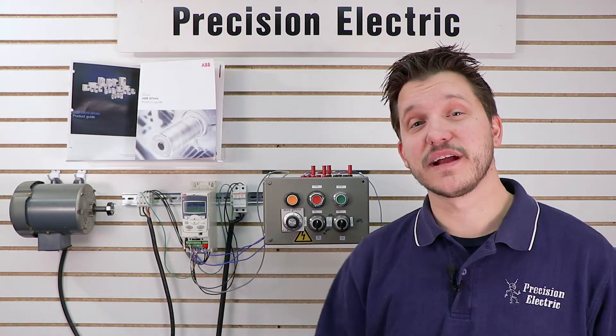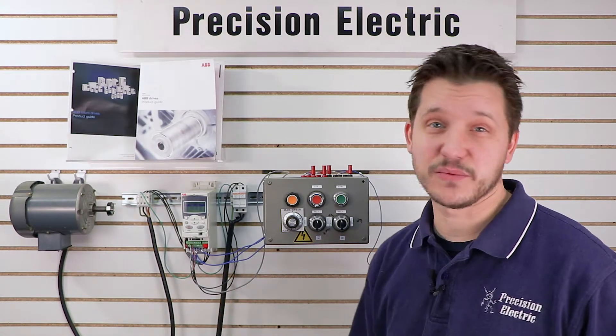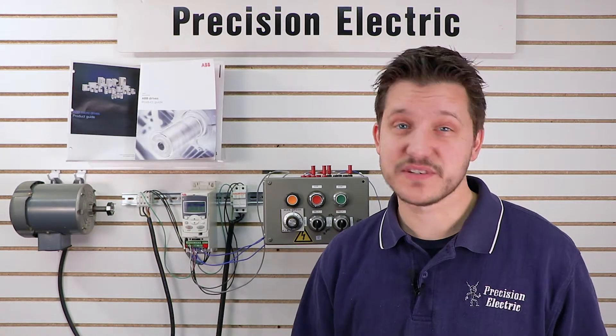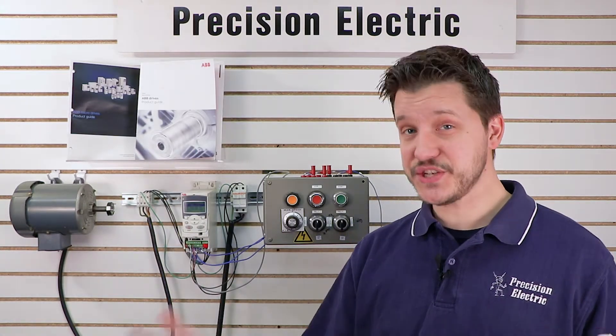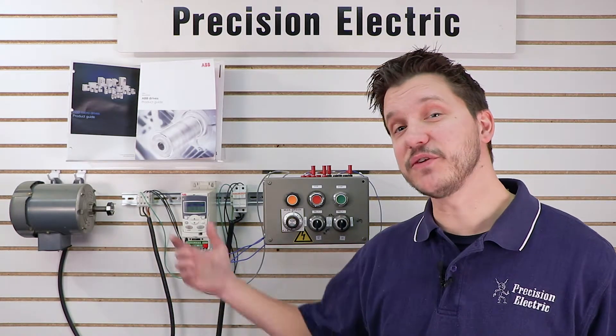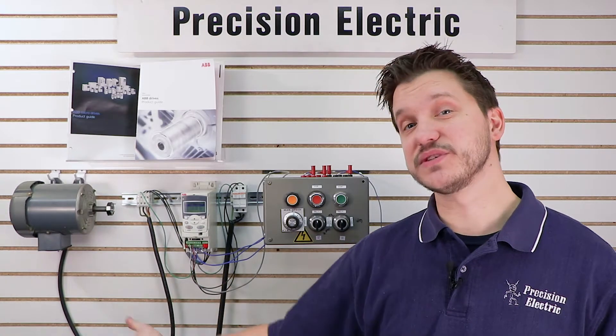This video is going to cover a more advanced feature of the ABB ACS 355 variable frequency drive in which we're going to actually tune it. Standard drives don't come pre-tuned because tuning requires a connection to your motor, so after you've wired your drive up and connected it to the motor, we can go through the tuning process.